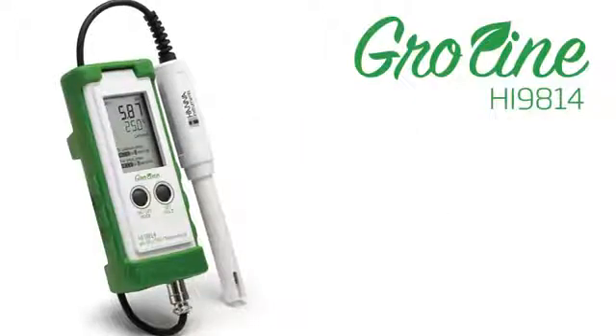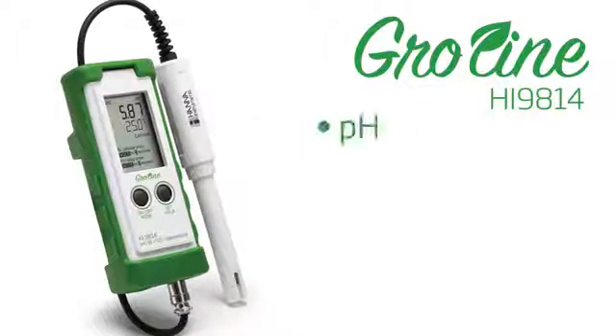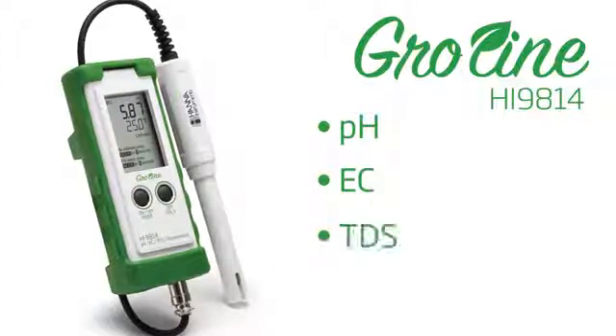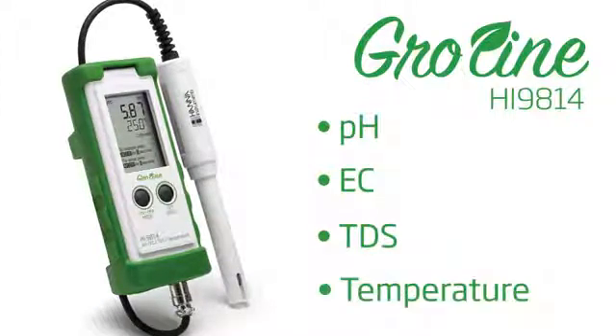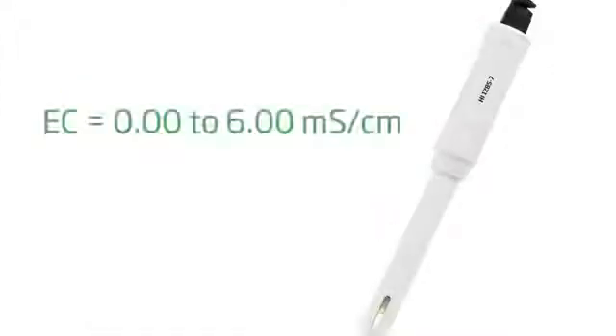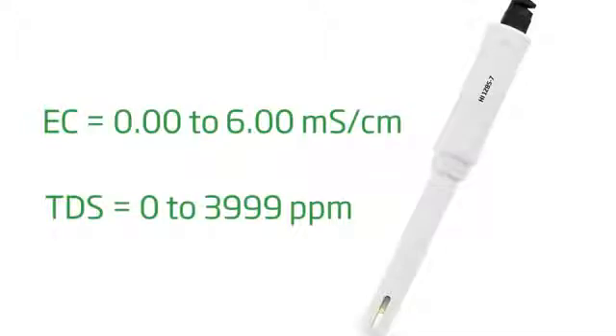The HI9814 GroLine Waterproof Meter measures pH, conductivity, total dissolved solids, and temperature with a single amplified probe that is immune to interference from humidity and electrical noise.